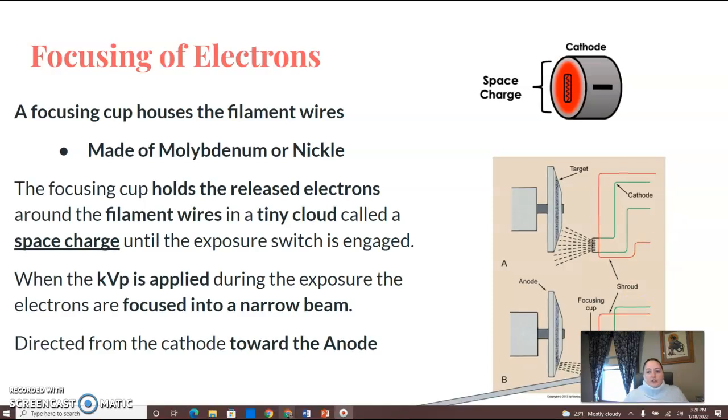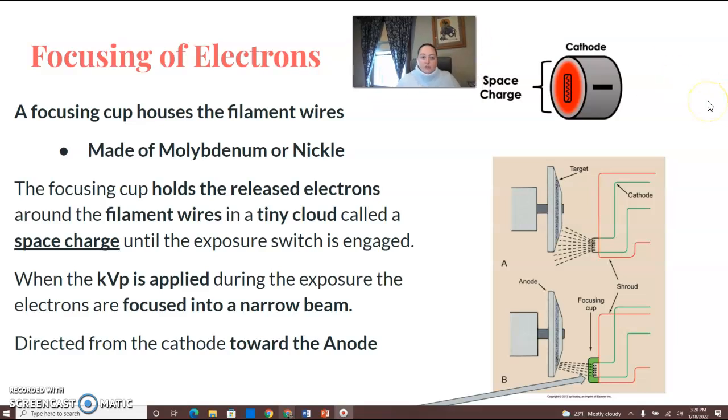You need a way to focus those electrons being accelerated across the tube. That's where the focusing cup comes into play. It houses the filament wires on the cathode end and is made of molybdenum or nickel. It holds the released electrons around the filament wires in a tiny cloud called the space charge until the exposure switch is engaged.